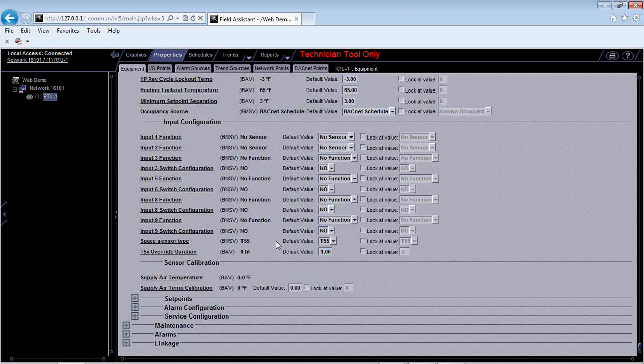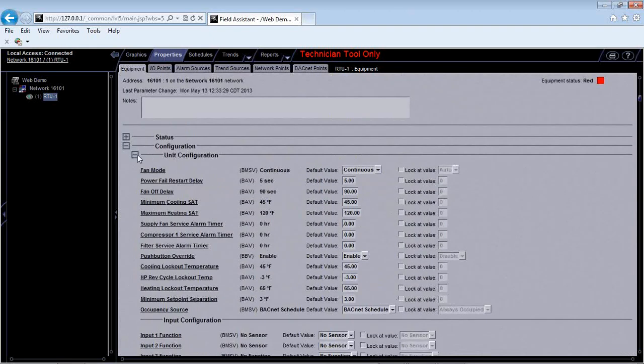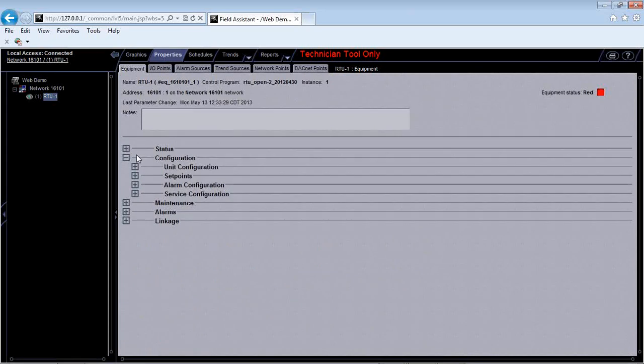So this sensor calibration is just giving you the supply air temperature reading. I don't have a supply air temperature sensor wired in right now, so I'm reading 0, but you can use it to calibrate if you want to change it. Usually, our supply air sensors have to be 10K Type 2 thermistors, and with thermistors you usually don't have to calibrate them. So it's there if you need to, if you have a messed up thermistor, but I would just recommend replacing it with how cheap they are.